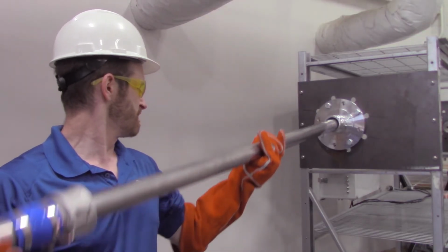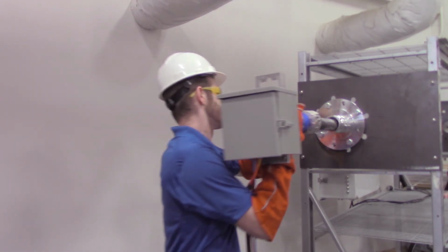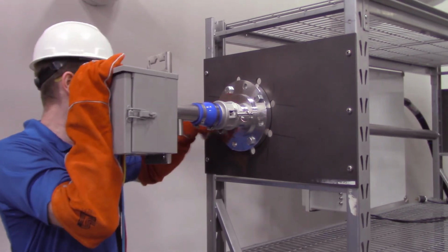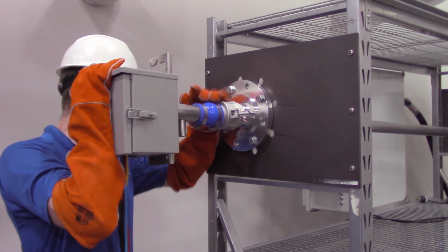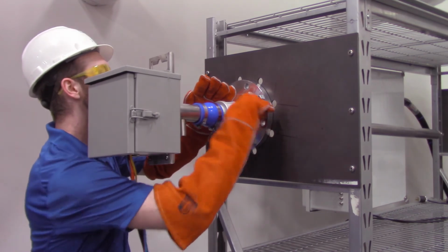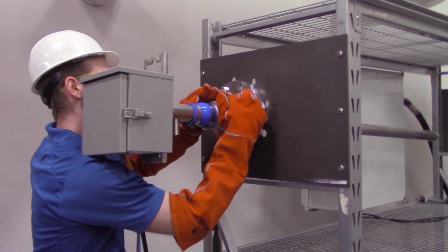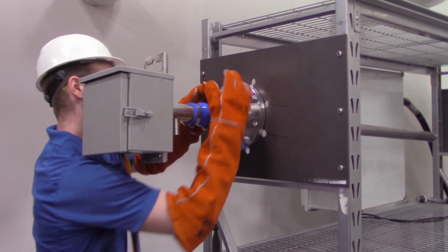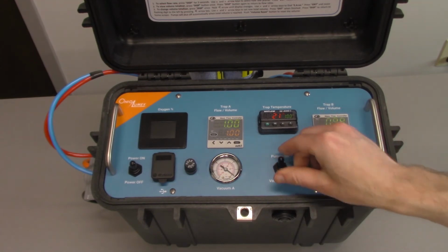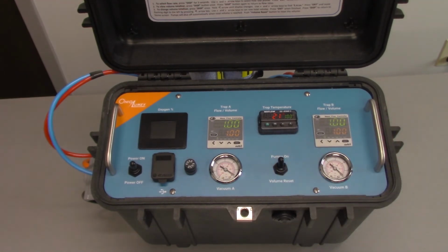Be careful not to break the traps while inserting the probe. Ideally, you should have some way of sealing the probe to the port, and there are a variety of ways to do this, including port stuffers, a flange with a 2-inch O-ring, or in this case, a cam lock adapter. Now that the probe is secure, turn the pumps on and wait for the sample volume to be reached.